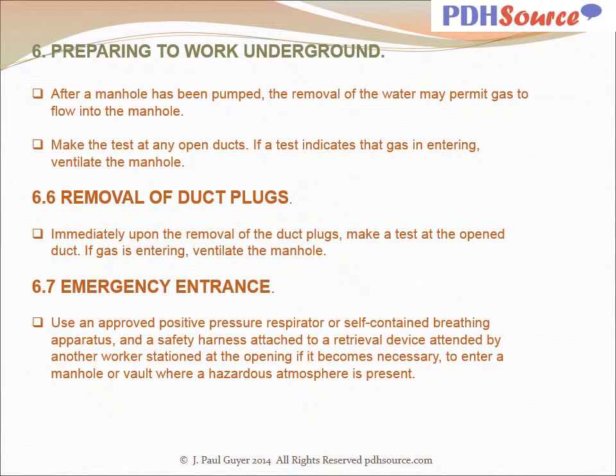After a manhole has been pumped, the removal of the water may permit gas to flow into the manhole. Make the test at any open ducts. If a test indicates that gas is entering, ventilate the manhole. Immediately upon removal of the duct plugs, make a test at the opened duct. If gas is entering, ventilate the manhole. Use an approved positive pressure respirator or self-contained breathing apparatus and a safety harness attached to a retrieval device attended by another worker stationed at the opening if it becomes necessary to enter a manhole or vault where a hazardous atmosphere is present.